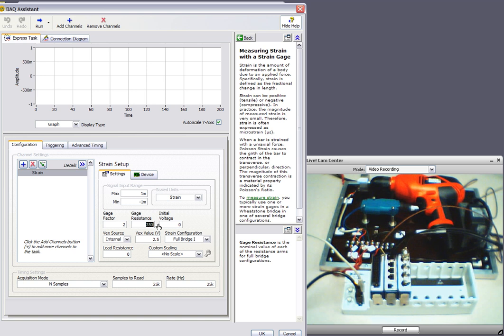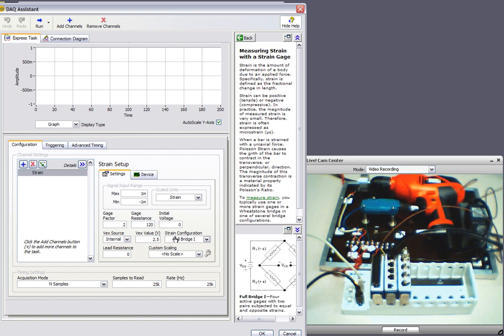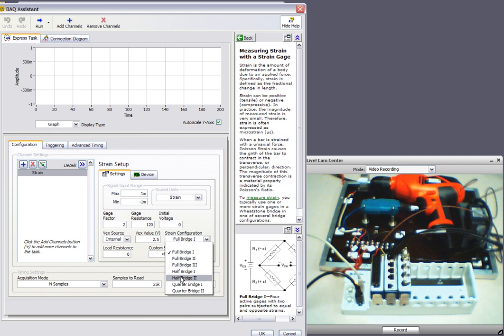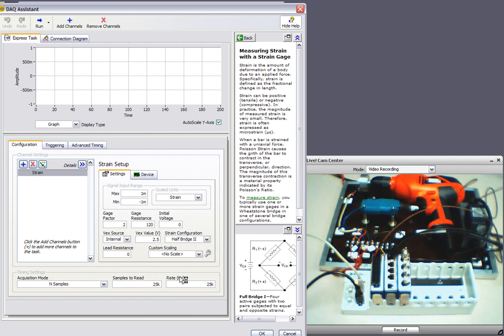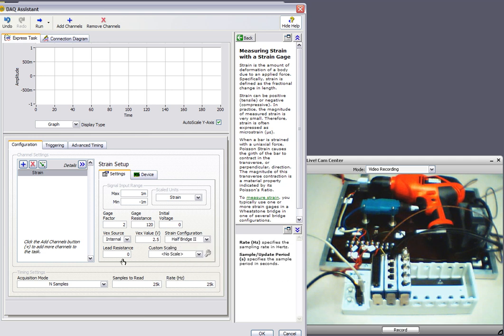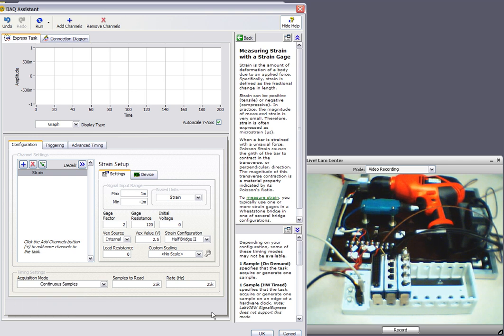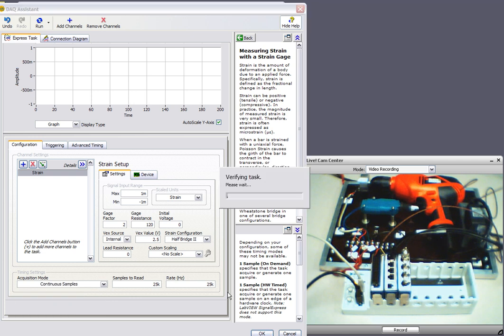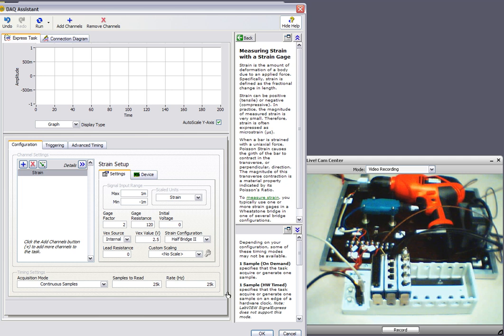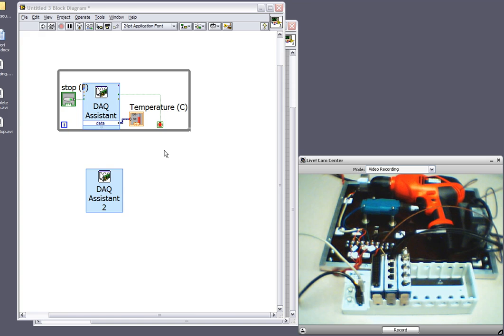So in this window, I can configure the strain gauge based on the sensor that I actually have. So I know it's in a half-bridge 2 configuration. And I also want to change my acquisition to continuous once again. I'll receive the same message and just select yes.